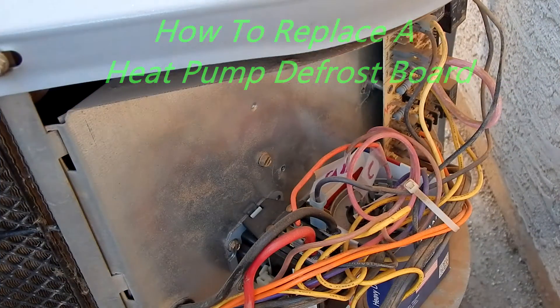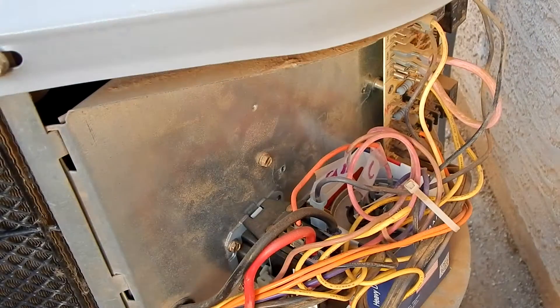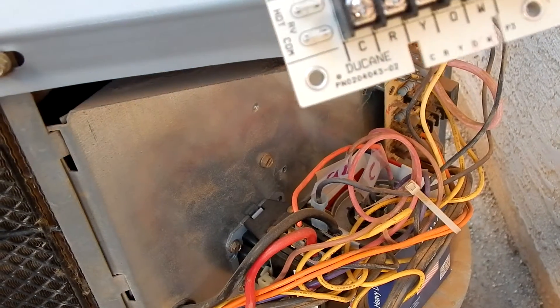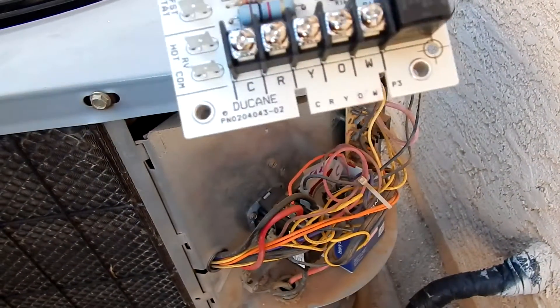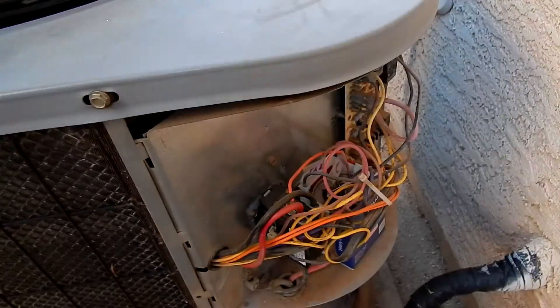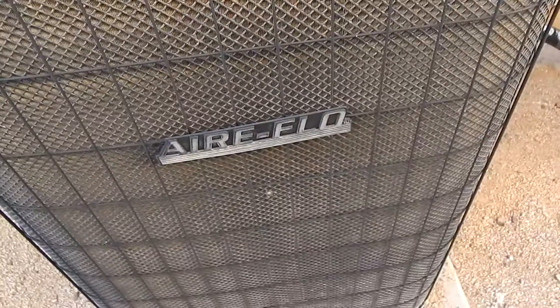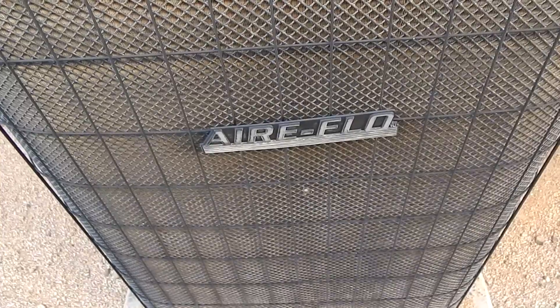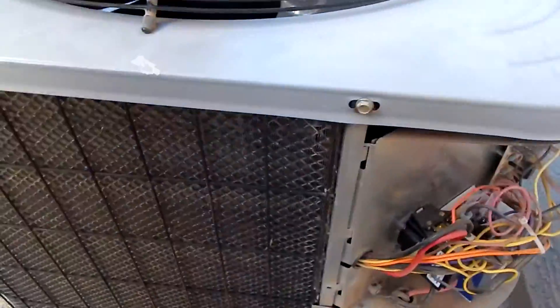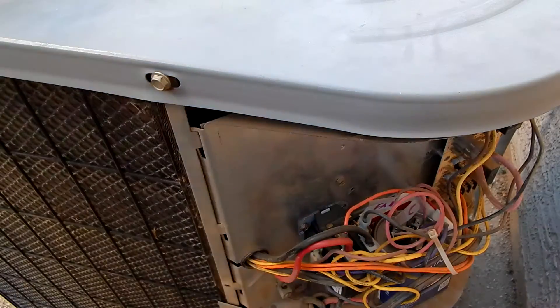Hello YouTubers, today I'm going to show you how to change out your defrost board in your unit like the one you see right here. I got the exact model board, and there it is. There's the defrost board. It's a Ducane board. I'll show you the part number in case you guys have the same exact unit. It's brand name is Aire-Flo, apparently made by Lennox. The problem you may want to replace the board for is because these relays can go bad.